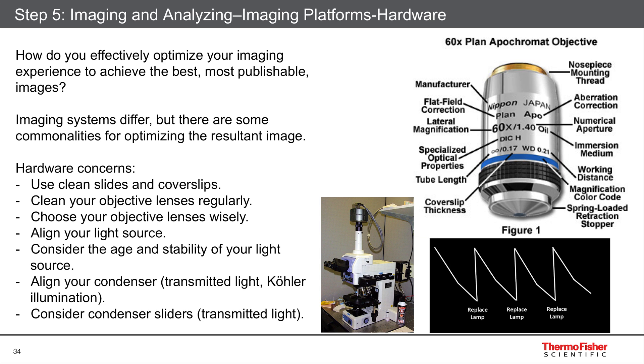What do you need to do with objectives and lenses to get the best, most publishable image? First, make sure your slides and cover slips are clean and dust-free before you begin your assay. Your objectives should be regularly cleaned and inspected, because dust, debris, or buffer dripped on them will reduce your resolution. And choose your objective lenses wisely, as I mentioned.